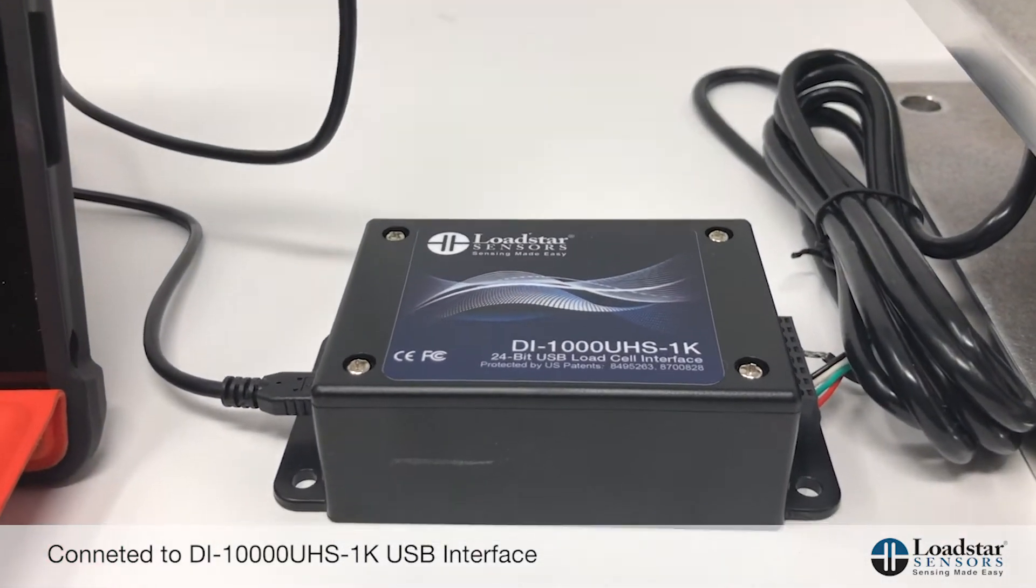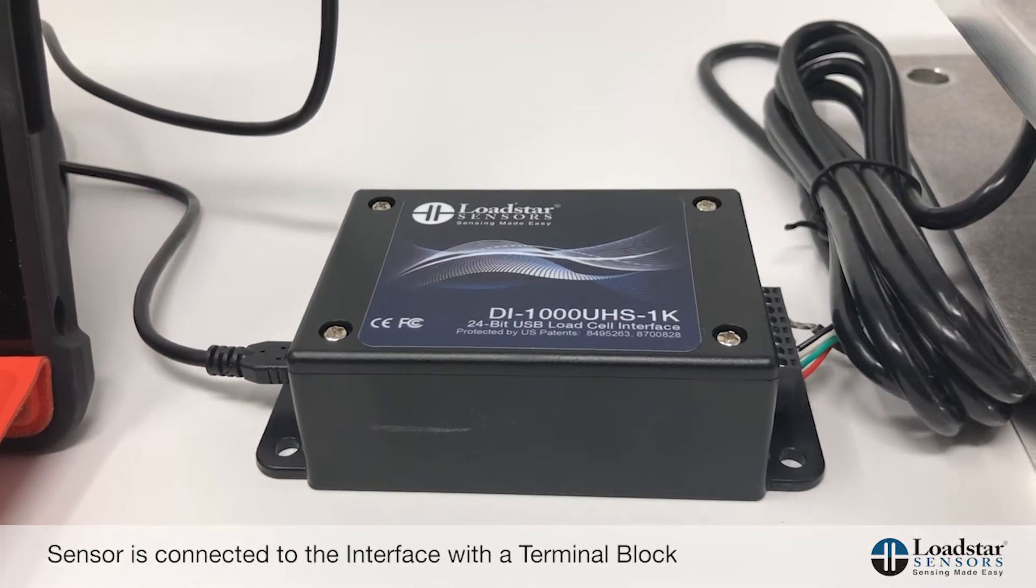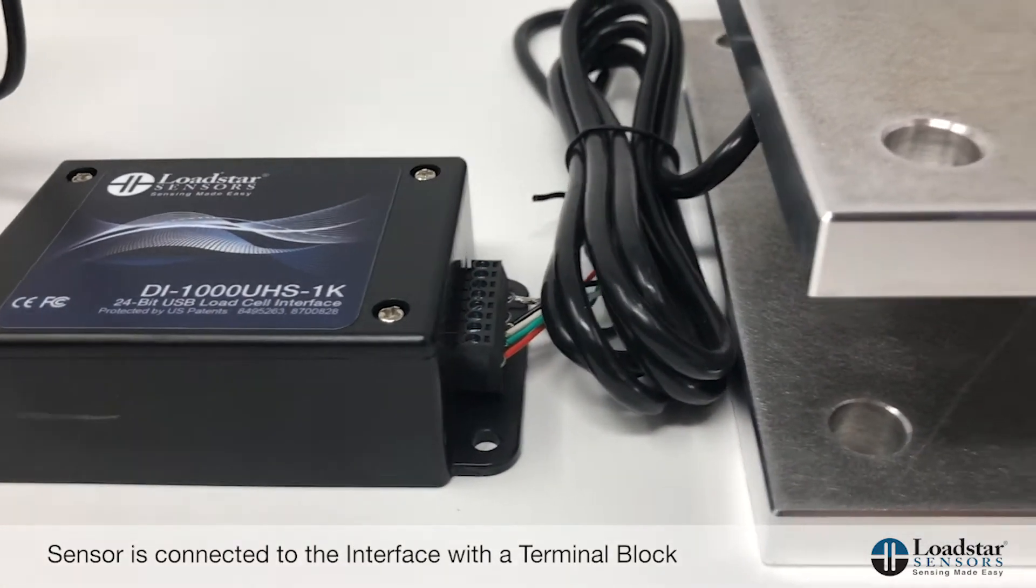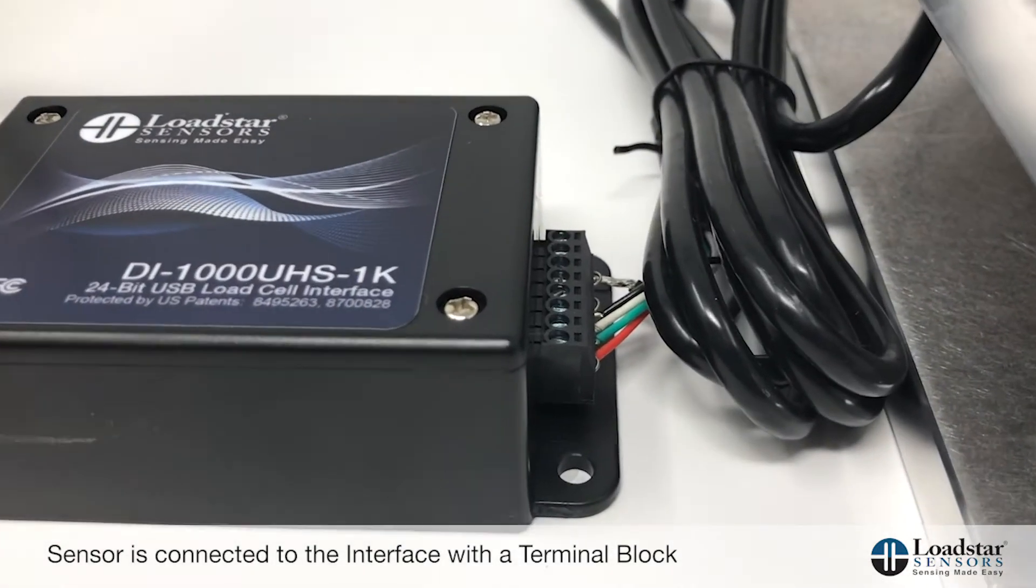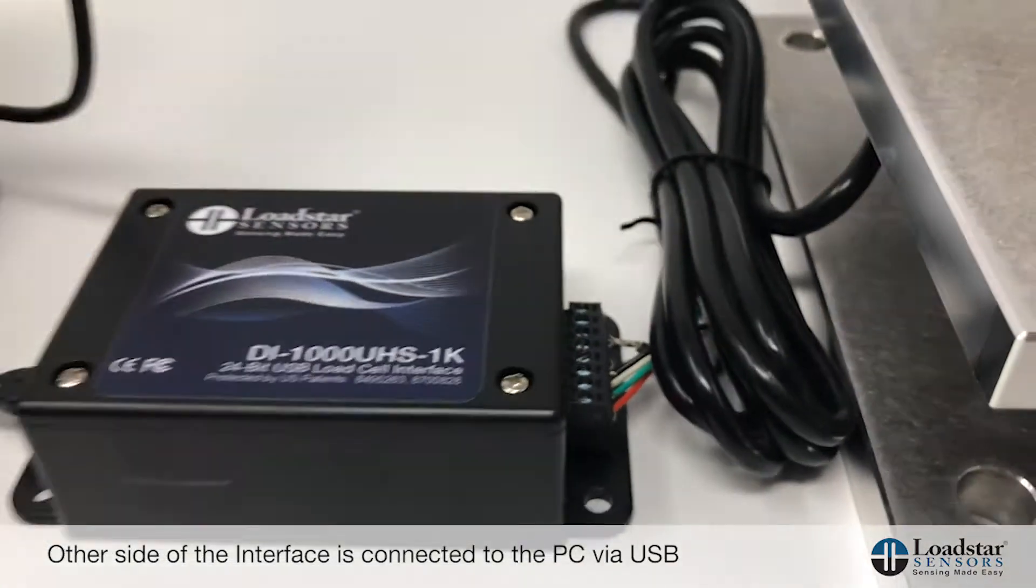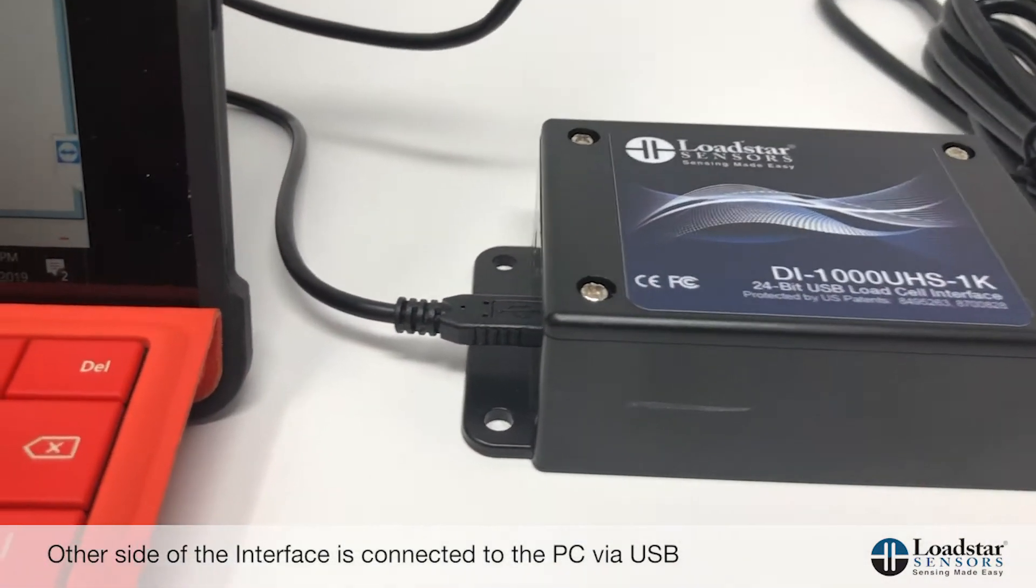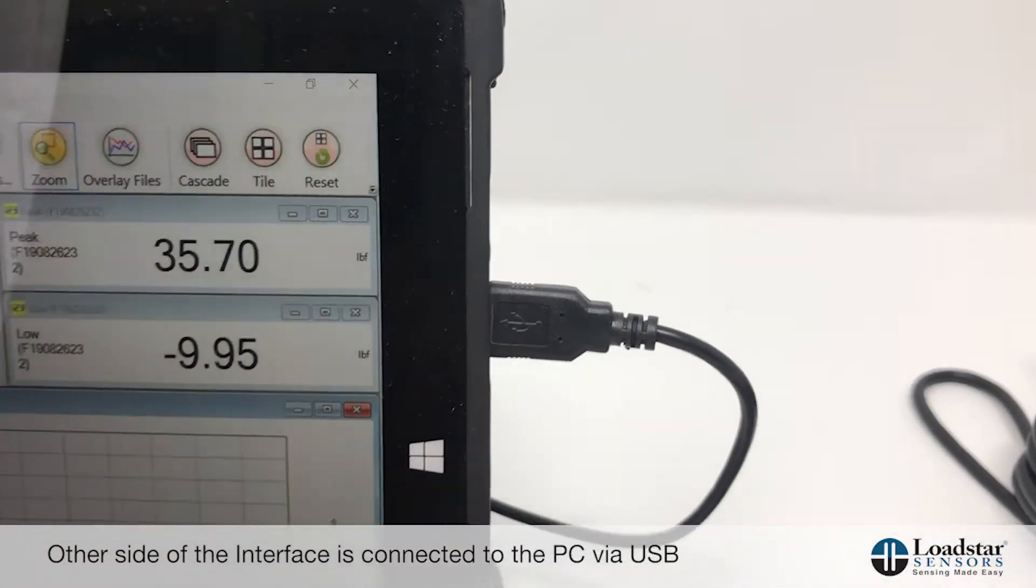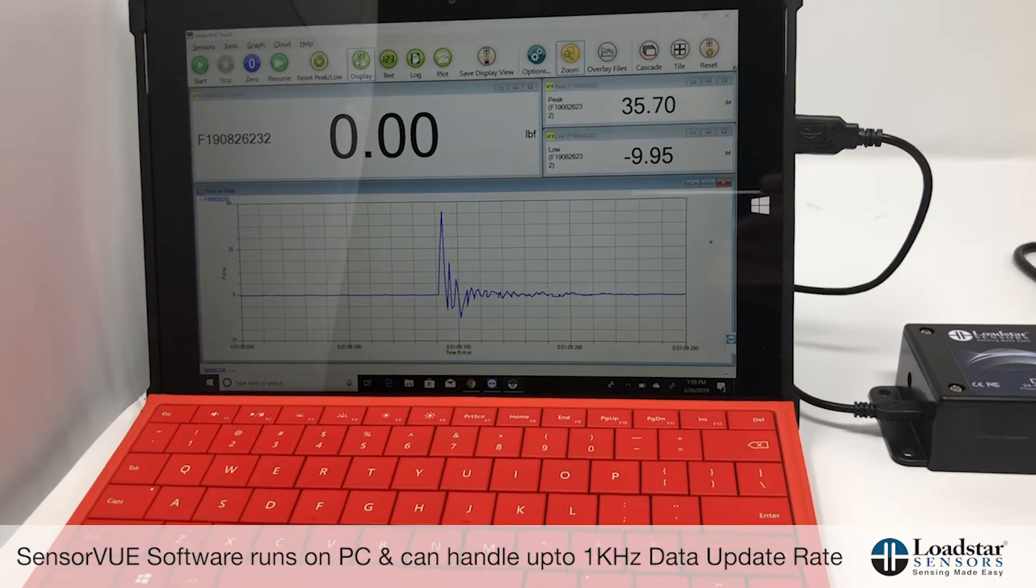It's connected to a DI-1000 UHS-1K USB interface. The load cell or sensor is connected to the interface through this terminal block, and on the other side of the device is our USB output. It goes directly into the PC, and the PC is running our SensorVUE software that can handle up to 1 kilohertz data update rate.